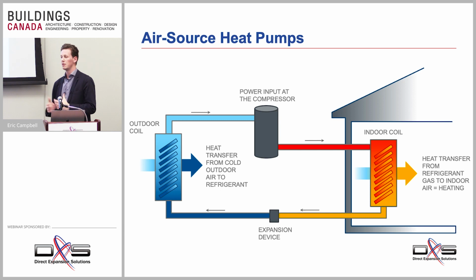And so in an air source heat pump, that compressor allows you to have very efficient heating and cooling at the indoor unit. So a heat pump, if you're familiar with a typical AC system, your split system with an outdoor condenser on your house and your indoor evaporator coil, a heat pump is similar to that, but instead of just being able to do cooling, it can also do heating. So we're actually drawing heat out of the air outside, and we're transferring that through the use of energy input at a compressor, and we're actually able to transfer that heat to the indoor coil. And now we can heat our space just using electricity, as opposed to using a furnace, which is using gas, and here we're interested in reducing our greenhouse gas emissions.